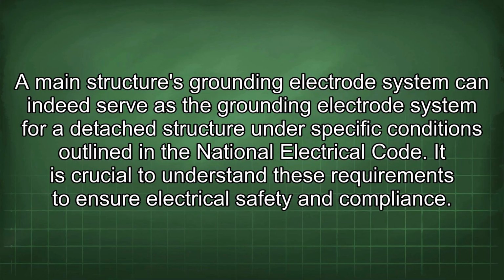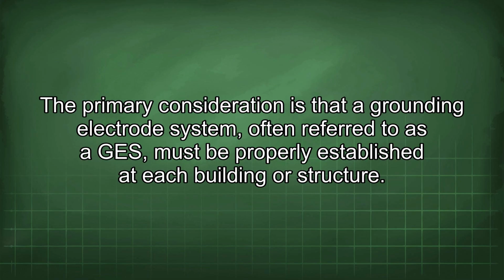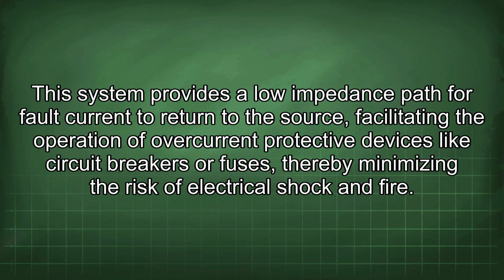A main structure's grounding electrode system can indeed serve as the grounding electrode system for a detached structure under specific conditions outlined in the National Electrical Code. It is crucial to understand these requirements to ensure electrical safety and compliance. The primary consideration is that a grounding electrode system, often referred to as a GES, must be properly established at each building or structure. This system provides a low impedance path for fault current to return to the source, facilitating the operation of overcurrent protective devices like circuit breakers or fuses, thereby minimizing the risk of electrical shock and fire.